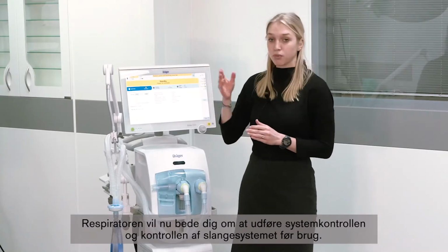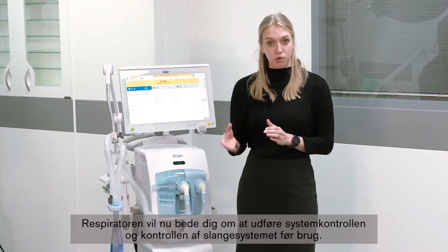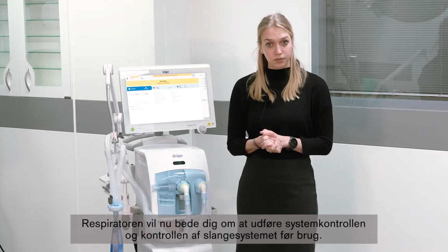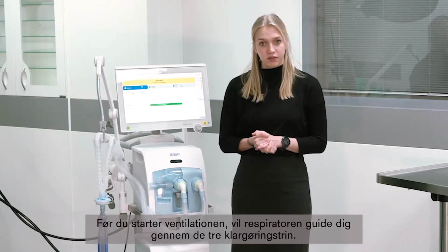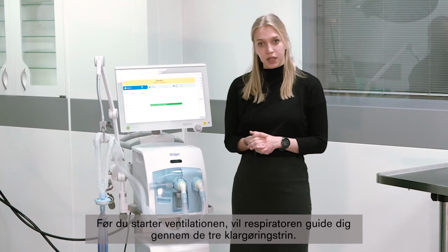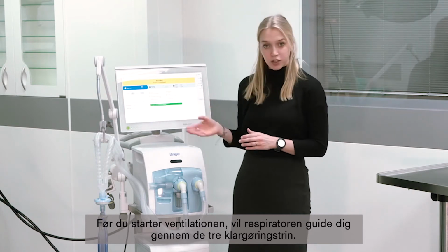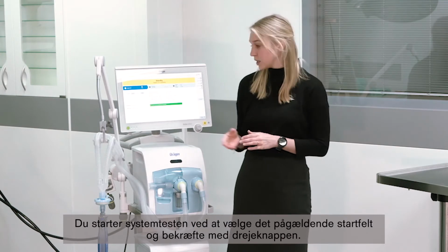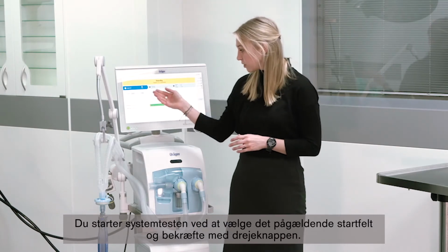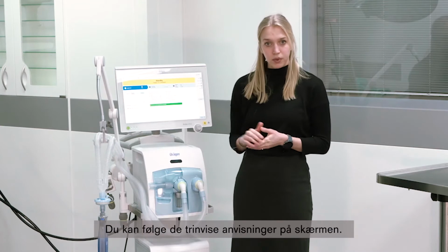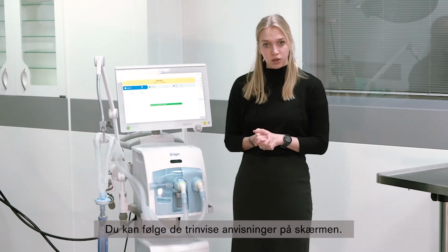The ventilator will prompt you to perform the system check and the breathing circuit check prior to use. Before starting ventilation, the ventilator will guide you through the 3 steps of preparation. To initiate the system test, please select the respective start field and confirm with the rotary knob. You can directly follow the instructions on the user interface.